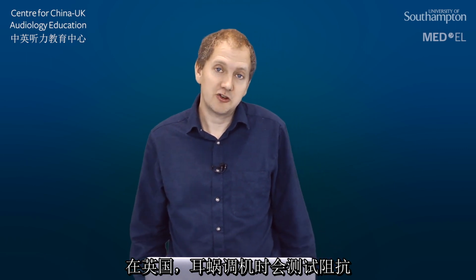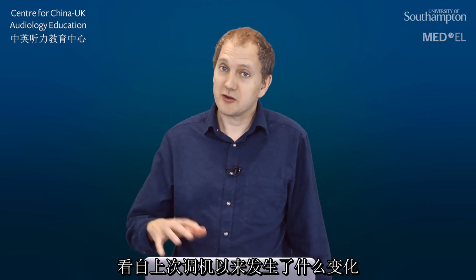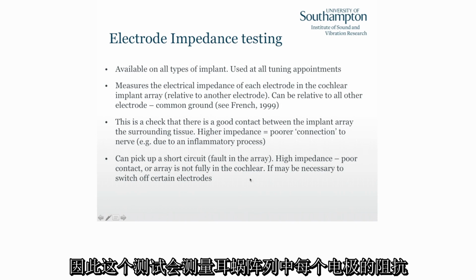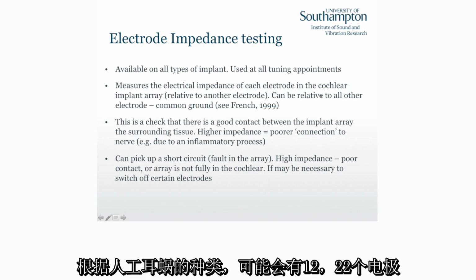So this is available on all types of implants, and certainly in the UK it's used routinely at tuning appointments to see if there's change from the previous appointment, to see if any electrodes in particular have got problems on them. So what the method is doing is measuring the impedance of each electrode in the array, the cochlear array.